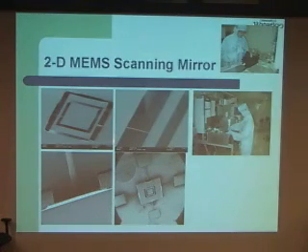They're suspended by two pairs of torsion bars, and the outer torsion bars have a length of around 200 micron, 6 micron in width, and only 1 micron in thickness. To put that into perspective, it's almost like suspending an entire soccer field on two planks, of which the smallest dimension is only 8 centimeters.